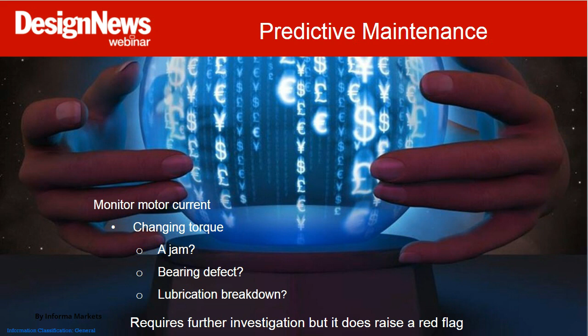So the key thing is now there's a problem, so your drive can send an alert. As we talked about before, it's also got the ability to apply filters to try to improve the situation in the meantime. But you've got the right people with the right information in their hands, because everything is connected. They're able to look at it, potentially over a web server, and potentially dial back in, although I know there are concerns about that in some quarters. But the point is you don't have to have somebody standing in front of the machine at the right time, and you don't find out late.